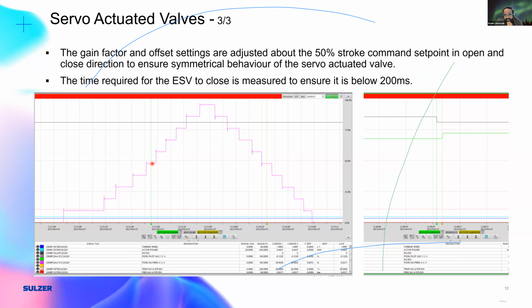And then after I'm done, I have to make sure that in case of an emergency, the emergency shut valve closes in under 200 milliseconds. So typically I would command 100% and physically go to the valve and disconnect the command cable. And the emergency shut valve is usually a spring-loaded valve, what we call fail-safe close. So once you pull out the cable, it should close within the 200 millisecond test. And this usually is done to ensure that we do not have any introduction of gas into the system when we have an emergency situation and need to shut down.